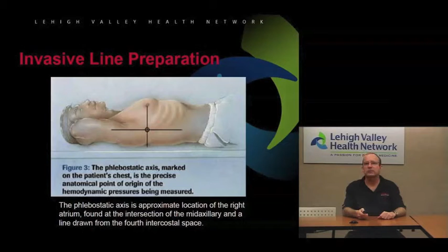To zero the line, open the system to air by turning the lever of the stopcock closest to the transducer towards the patient. And just something to keep in mind with the stopcocks, they can be confusing, whether we're using them for umbilical lines, for transducing pressure lines, whatever. Just remember the shutoff: whichever way the lever is pointing is where it's shut off. So when it's shut off towards the patient, that means there won't be any blood backing up into your line.